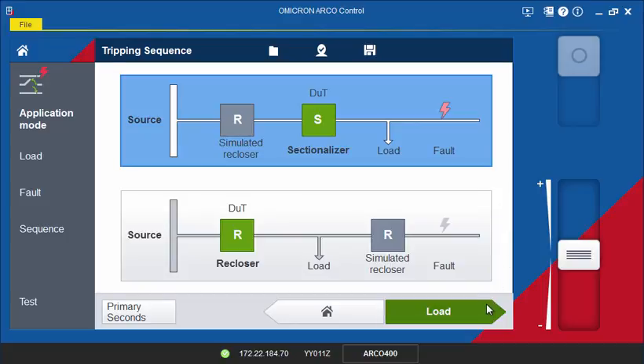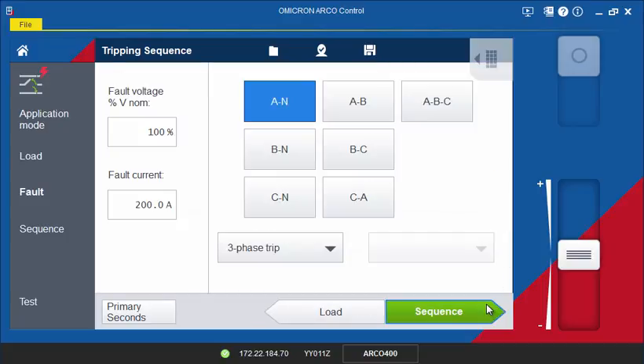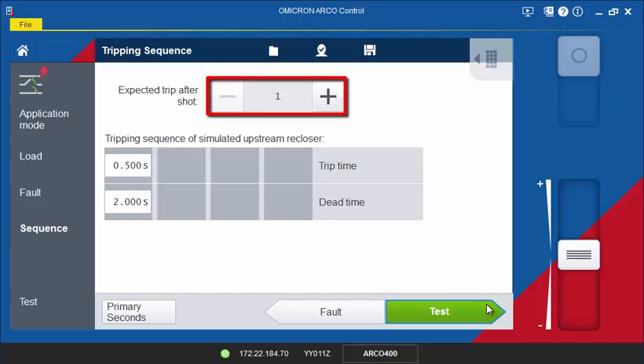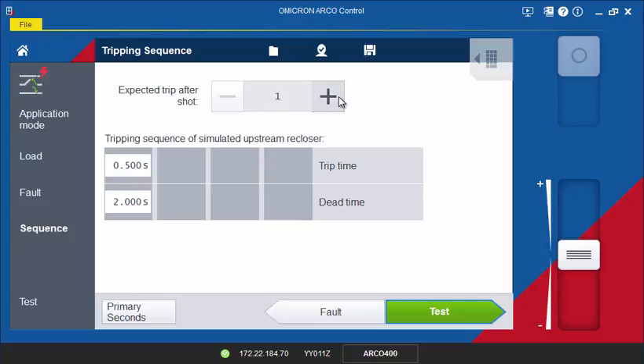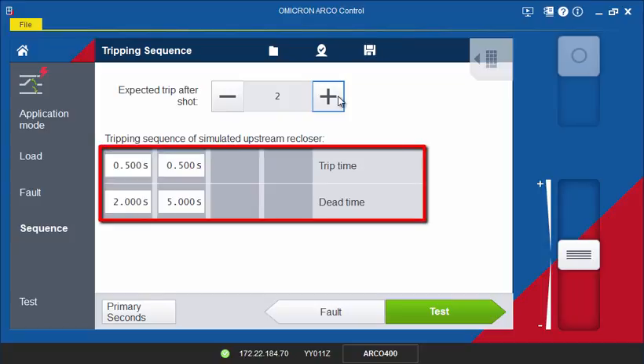On the next two pages, define the pre-fault and the fault state that are specified as in the recloser mode. In the sequence screen, use the expected trip after shot field to define the cycle during which the sectionalizer is expected to trip. For example, if set to two, tripping of the sectionalizer is expected during the dead time of the second cycle of the simulated upstream recloser. The trip and dead times of this simulated recloser are defined in the table below.